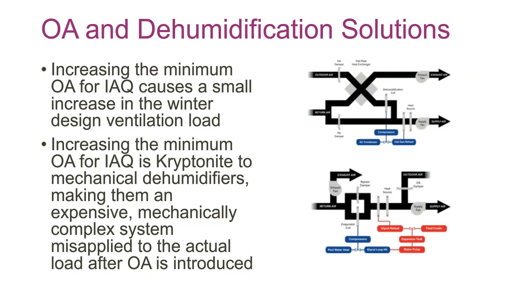So when you look at the two different solutions we've been talking about, the outside air unit, all you get is a small increase in the ventilation load you can offset with your heat exchanger. I kind of joke it's kryptonite to a mechanical dehumidifier, increasing the outside air for indoor air quality, because then they're really just an expensive, complex system that's truly misapplied to the loads that you're experiencing for basically everything but summer. So it's really just the wrong system to be considering if you're going to do more indoor air or more outside air.